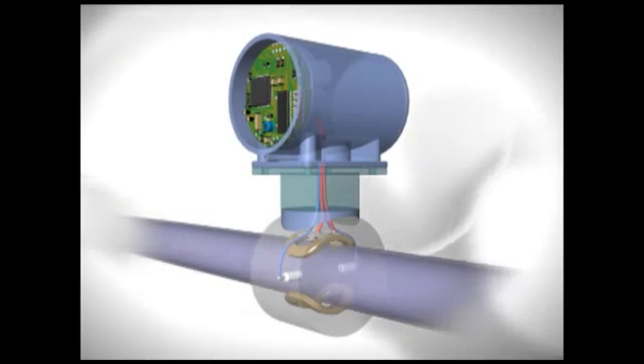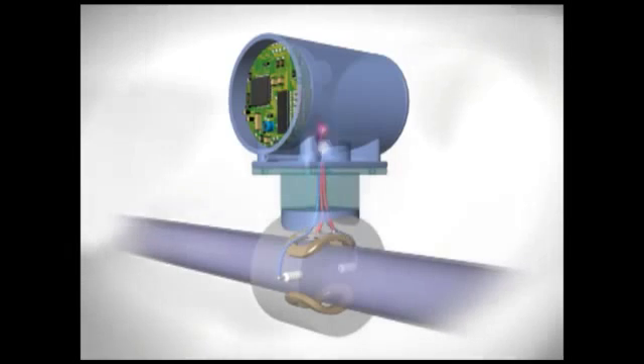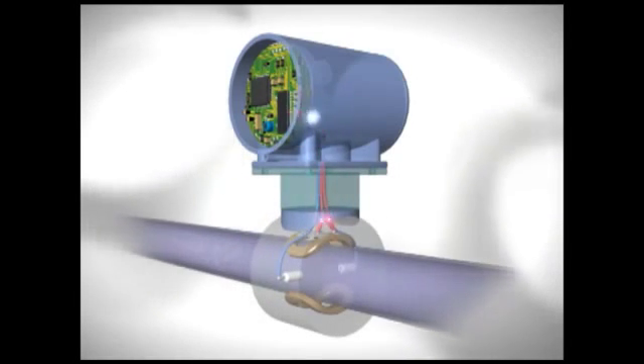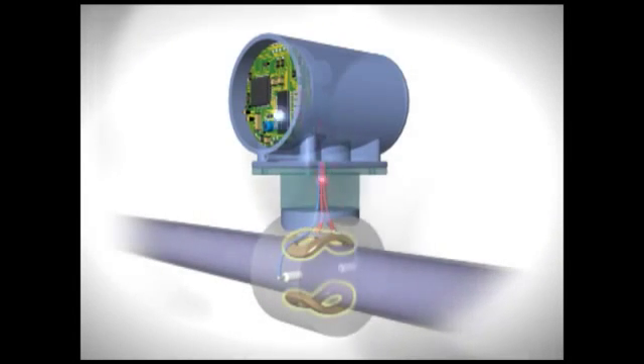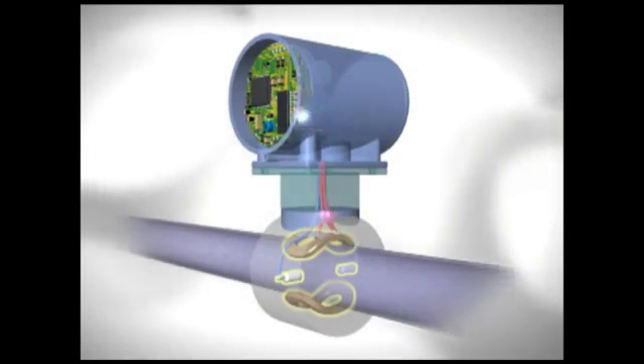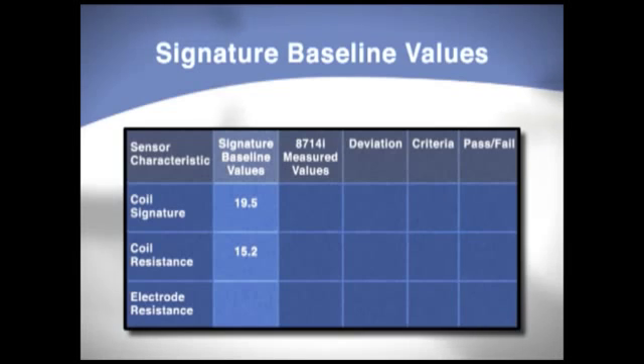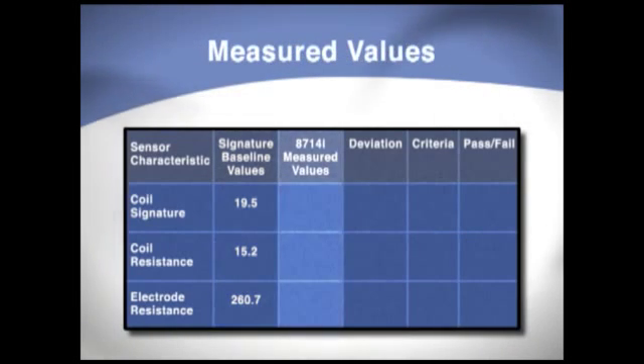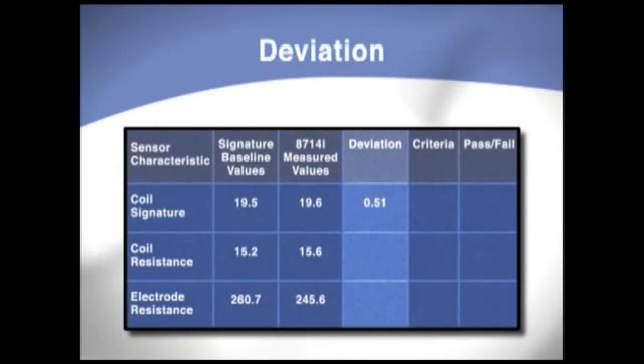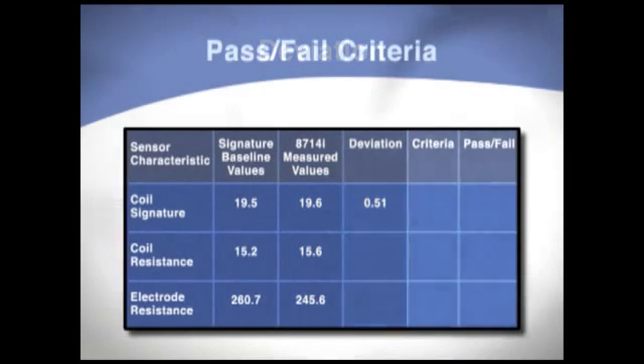At the time of initial calibration, the 8714i establishes a flow tube sensor signature for the coil circuitry and electrode circuitry and stores that information in non-volatile memory. This establishes a baseline of the meter's magnetics. Thereafter, every time the 8714i is run, it compares the measured values against the signature values and calculates the deviation. This deviation is then checked against your pass-fail criteria.